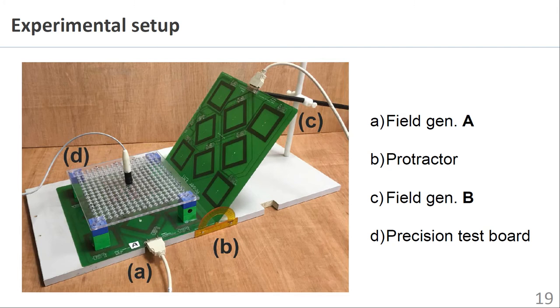This picture shows the actual experimental setup using the two field generators A and B. The tilt angle of field generator B, beta, is measured using a protractor centered at the fulcrum of rotation. A precision machined polycarbonate test board is used to precisely locate the magnetic sensor at known positions above field generator A.